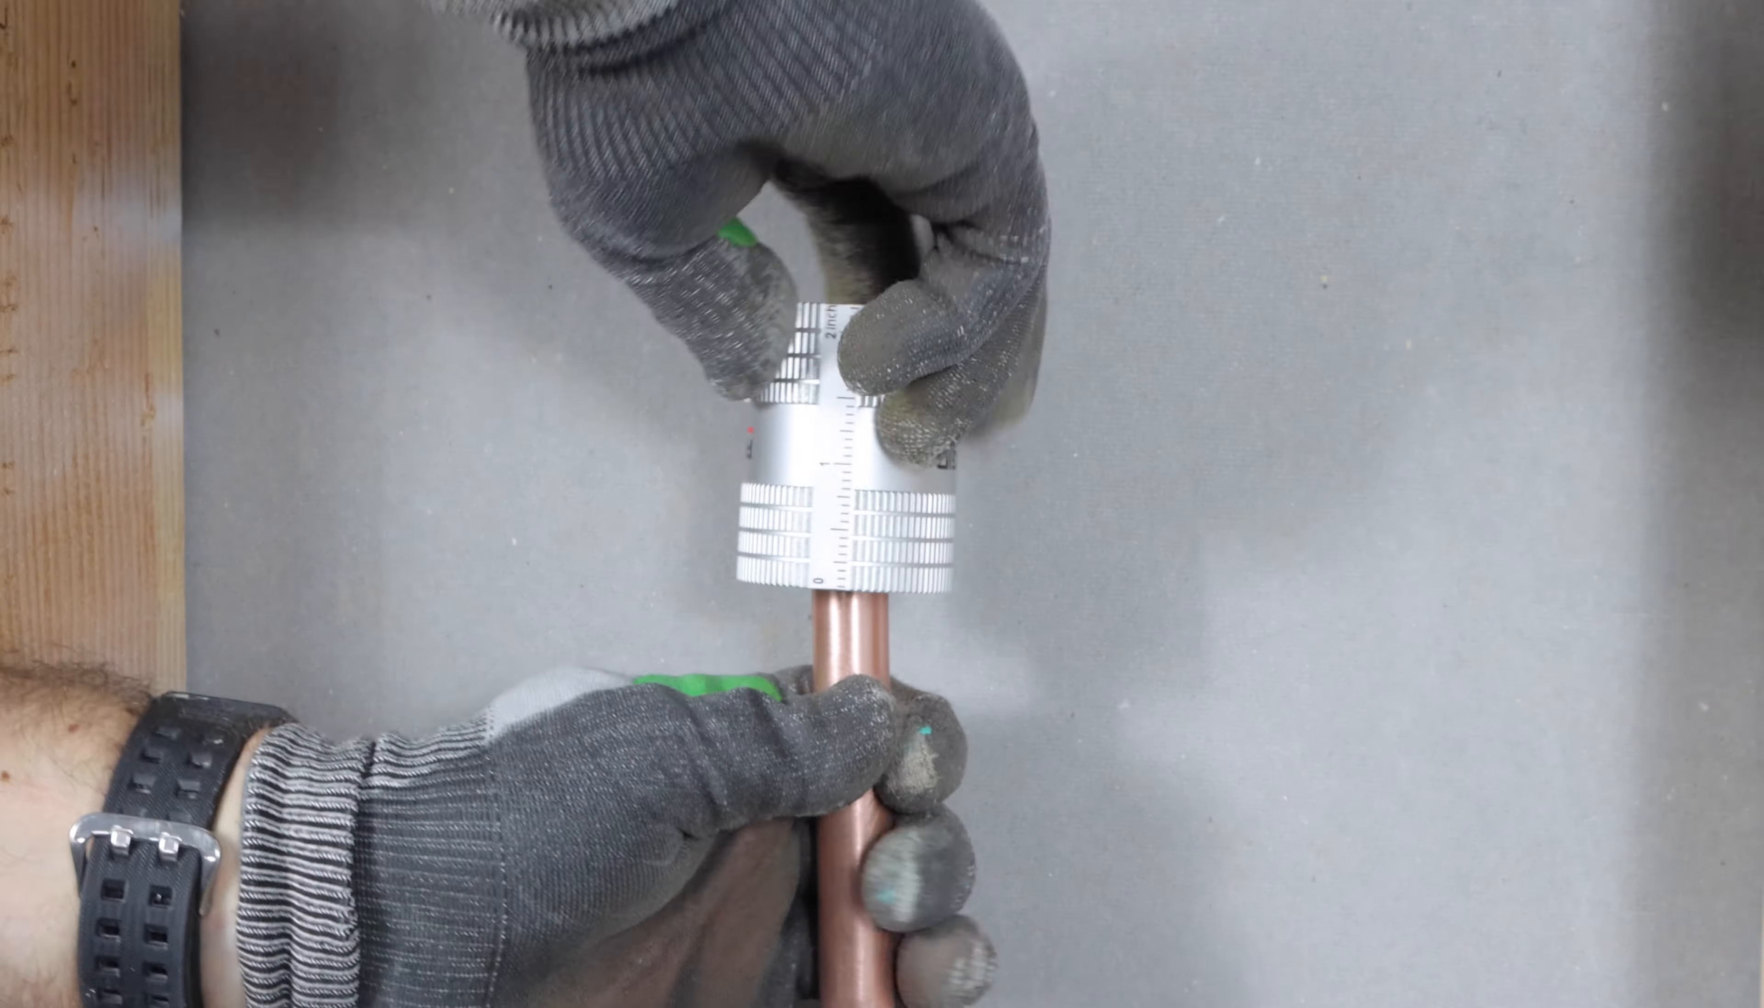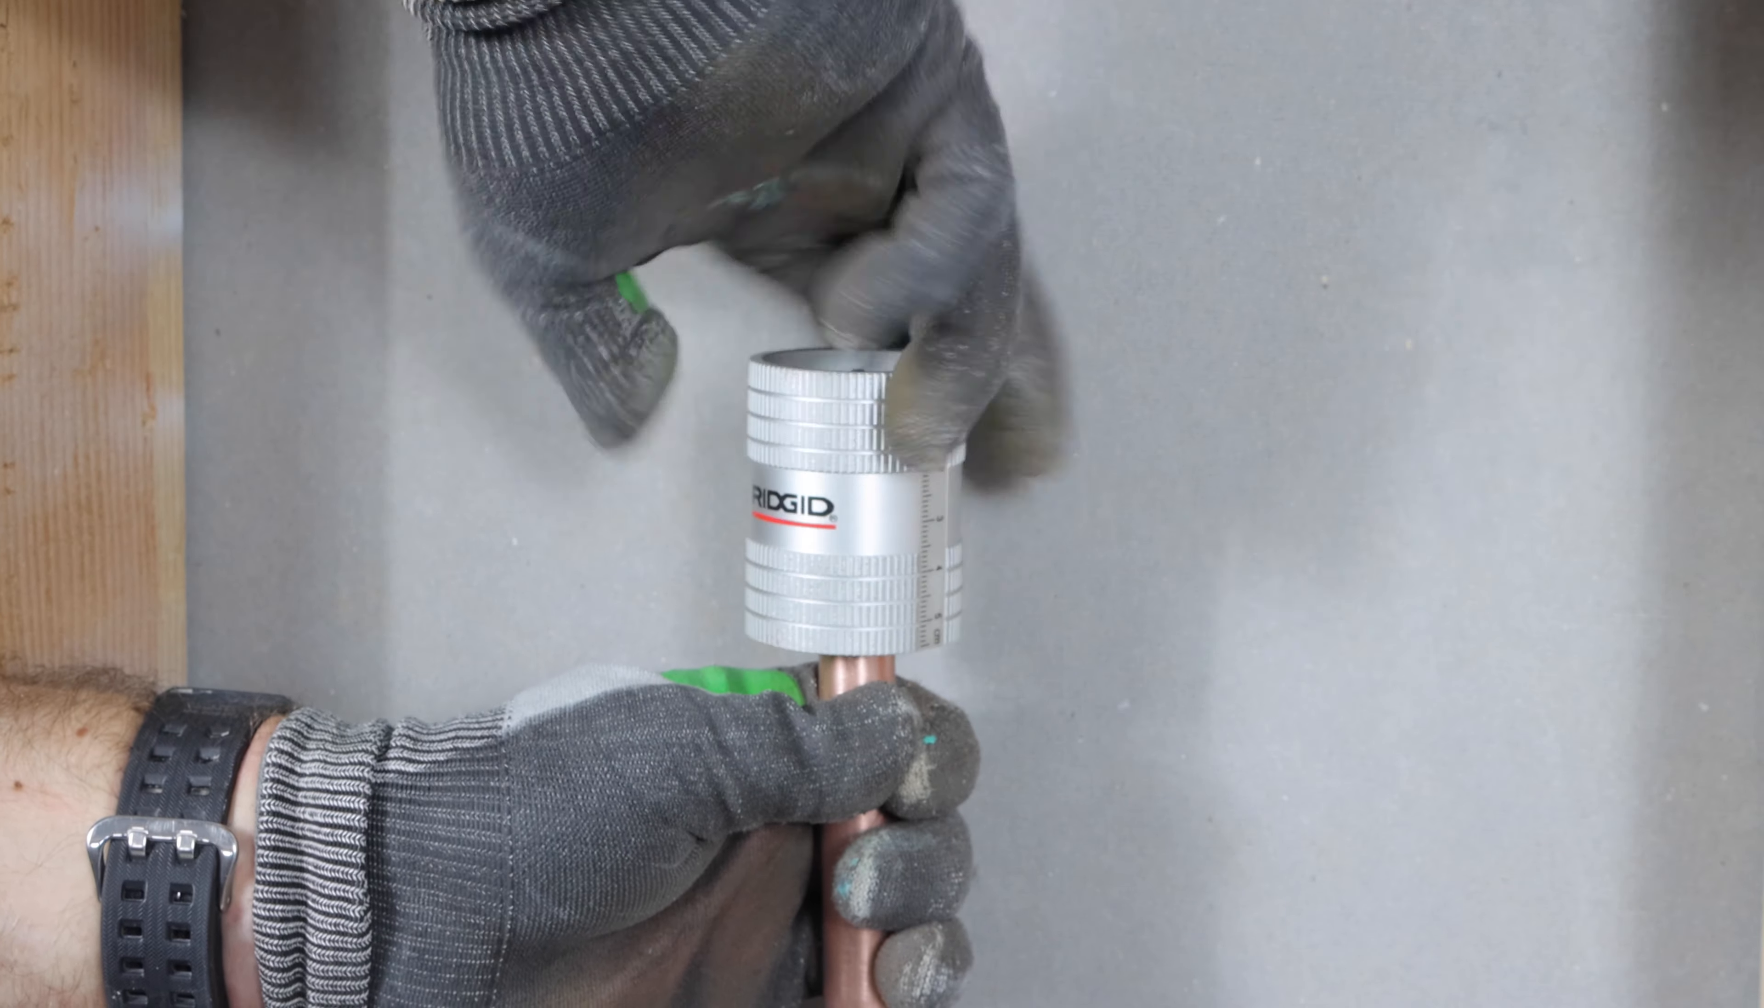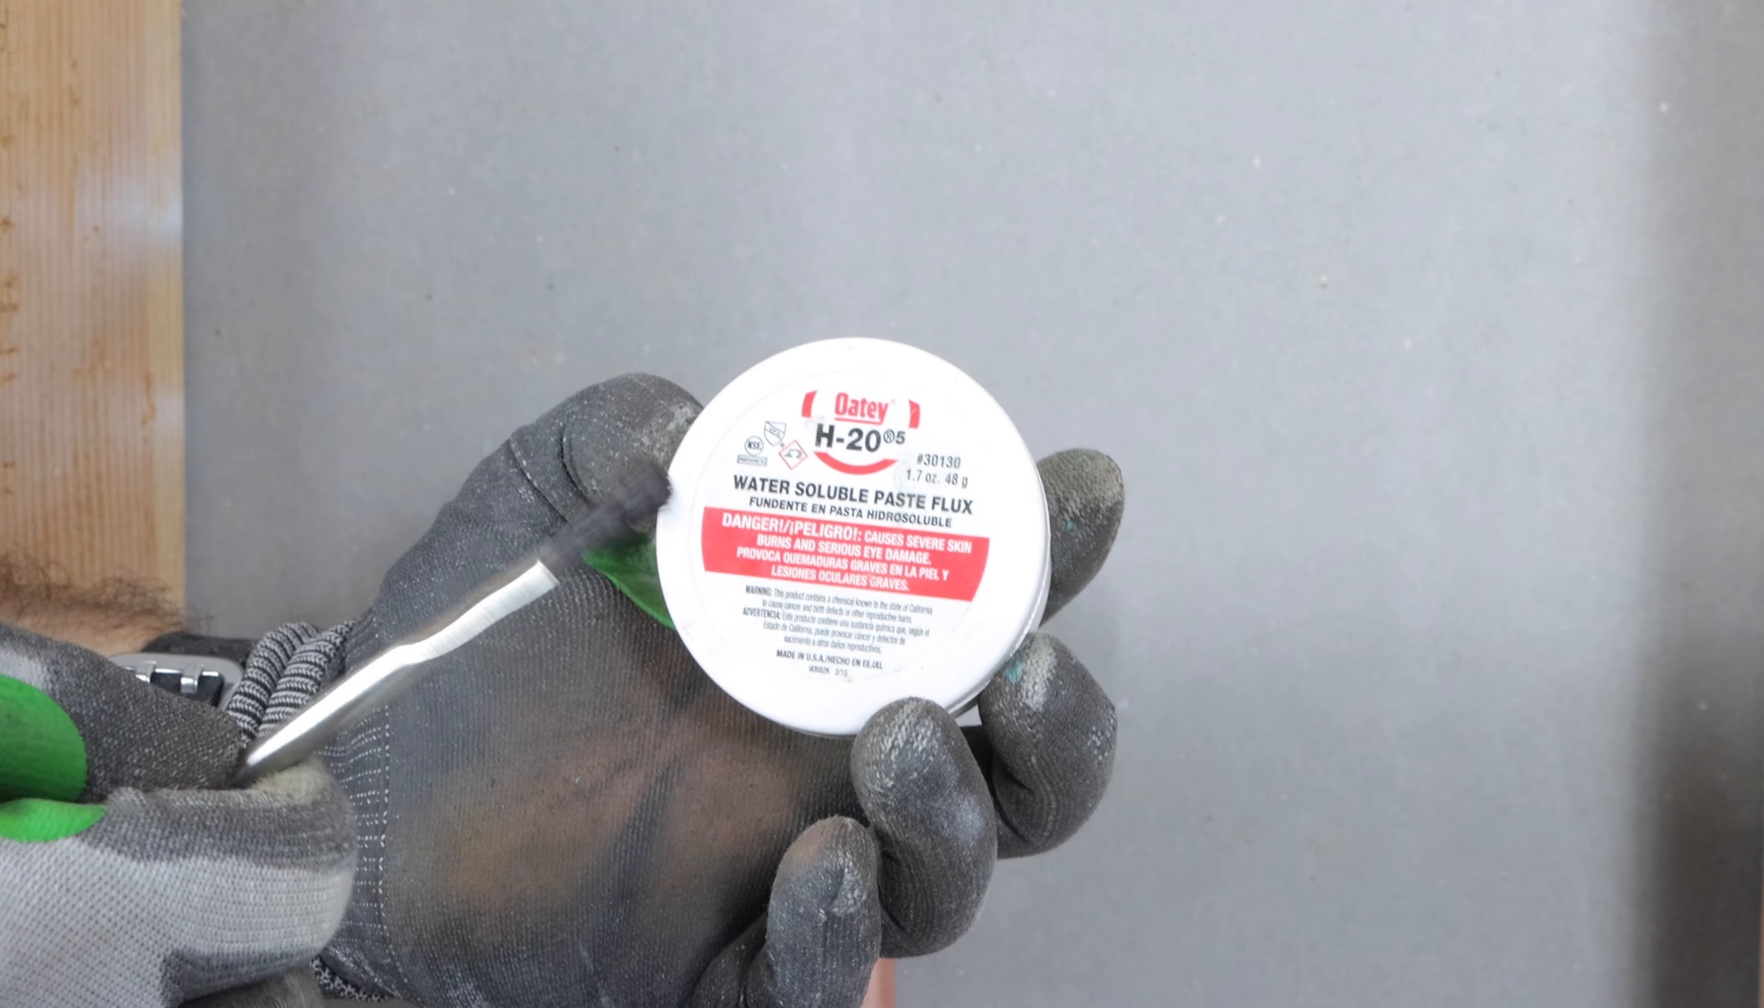The next step, and this is important, is to deburr the inside of the copper pipe. This is a RIDGID reamer. This deburrs both the inside and the outside of the copper pipe. So you want to do maybe like 10 to 15 revolutions both times. Then I hit that one more time with the nylon grit pad. That really just removes any of the burrs on there.